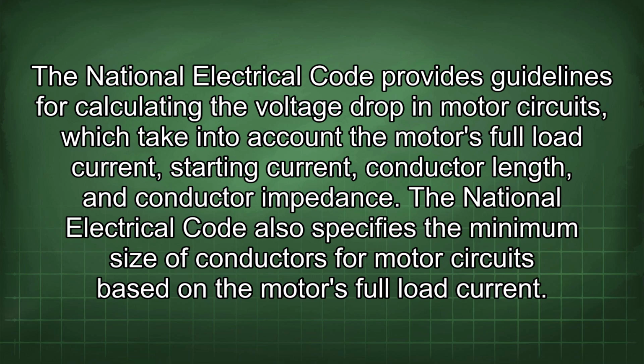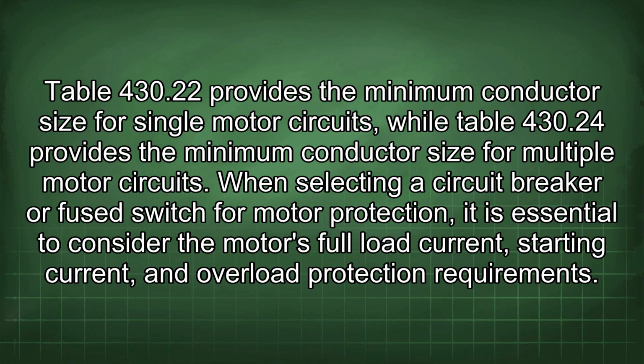The National Electrical Code also specifies the minimum size of conductors for motor circuits based on the motor's full load current. Table 430.22 provides the minimum conductor size for single motor circuits, while Table 430.24 provides the minimum conductor size for multiple motor circuits.